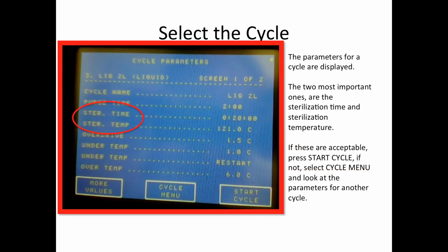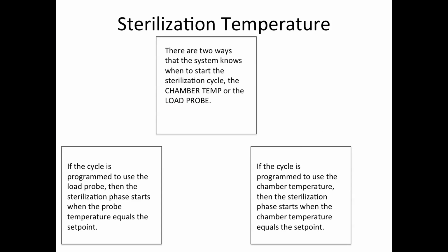The cycle parameters are displayed on this screen. The two most important ones on this screen are the sterilization time and the sterilization temperature. If these are acceptable, you simply press Start Cycle. If not, press the Cycle menu and you can look at the parameters for another cycle. Before we press the button and start the run, let's talk about the sterilization temperature.